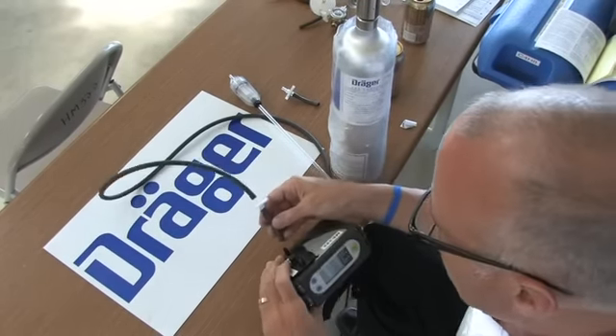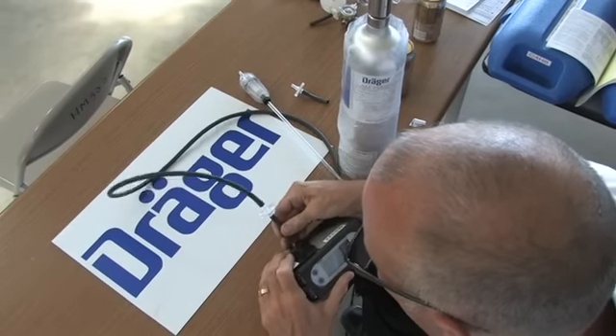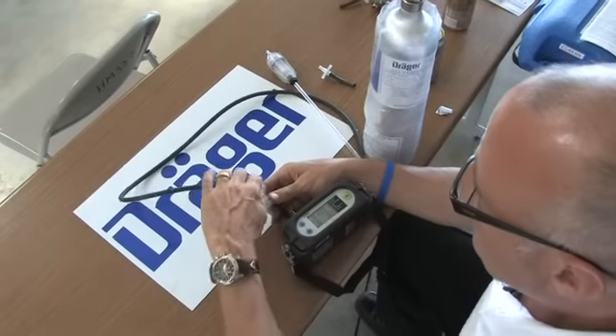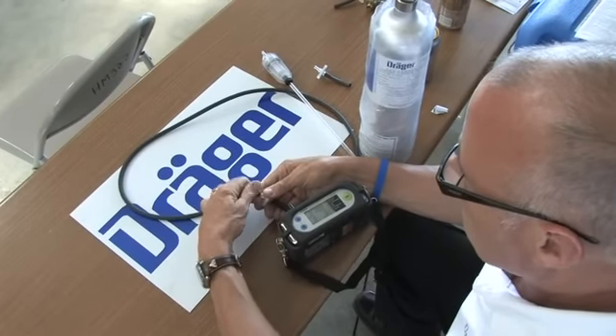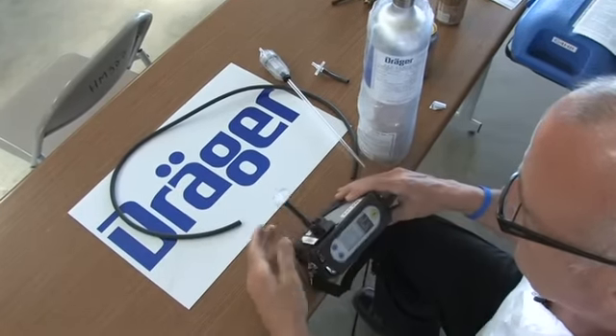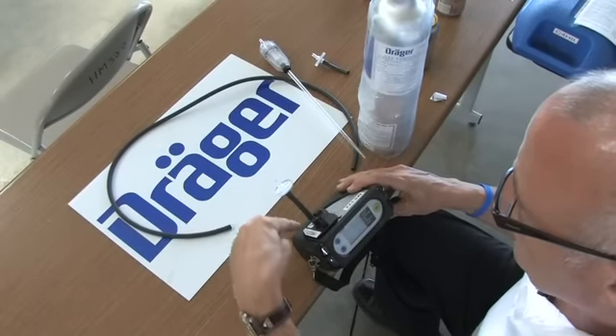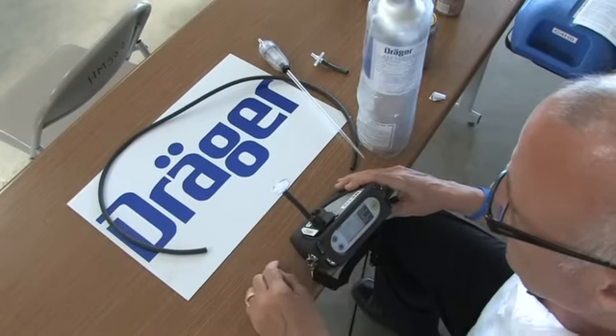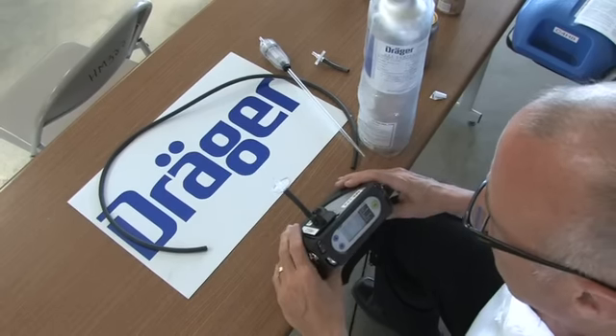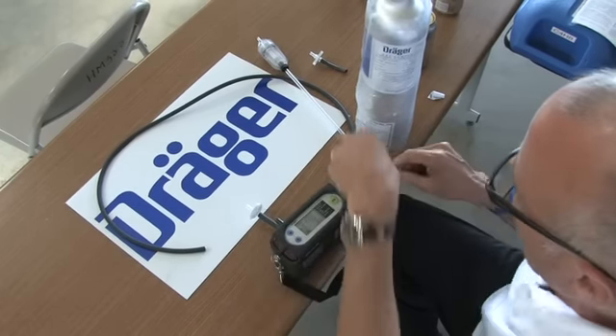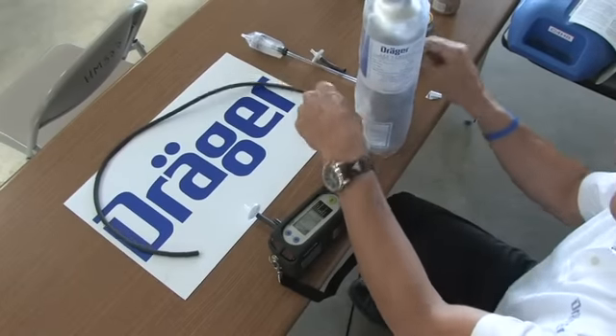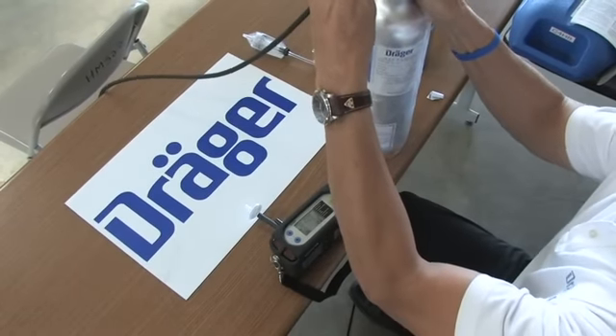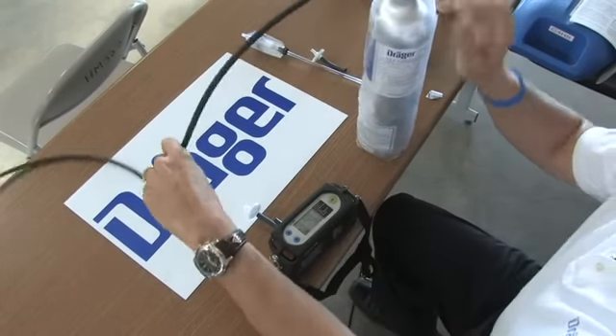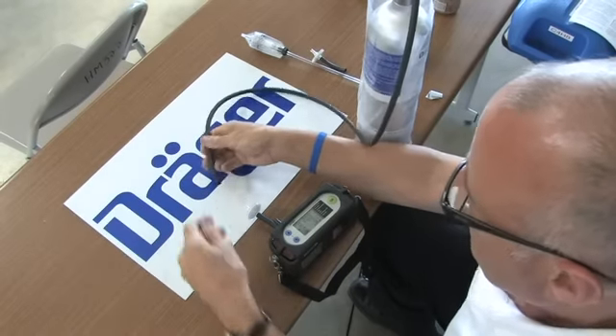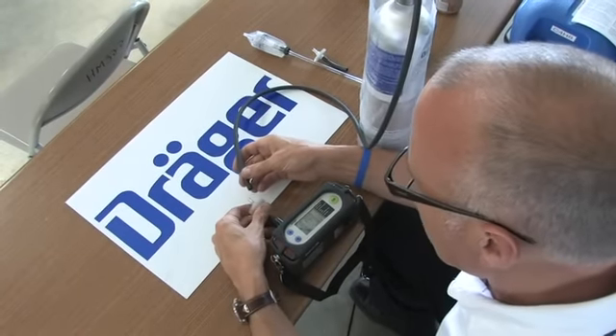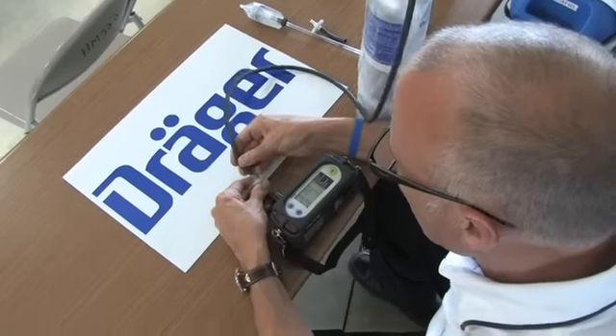Also with the pump running, you have to connect up a hose barb with a minimum of just a hydrophobic filter in place. This way, as the air is being aspirated in and then exiting this barb, I know that I'm not bringing any dust into the instrument, into the pump. So what I'm going to do now is connect up my hose line to my cocktail bottle demand flow regulator. And I'm now going to connect my cal gas. And we're going to do a bump test here to see what our readings are like. Here we go.